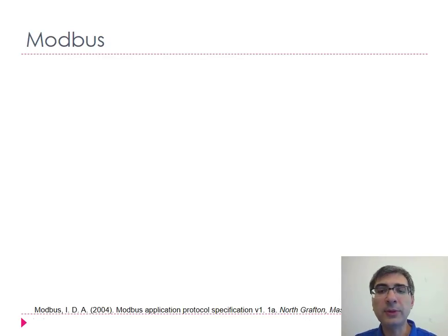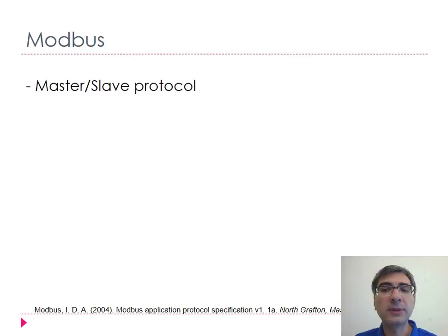In terms of the actual technologies used in industrial control networks, one of the first ones, a very old one, although not quite obsolete yet, I mean it's still used, is Modbus. Modbus is extremely simple. Its logic is simplicity, because simplicity provides performance, and simplicity also provides reliability to some extent. So Modbus is a master-slave protocol. That means that there is a master and there are slaves. In fact, in Modbus there can be only one master, and that one master tends to be, for example, a SCADA server. And the slaves might be the RTUs, the different remote telemetry units.